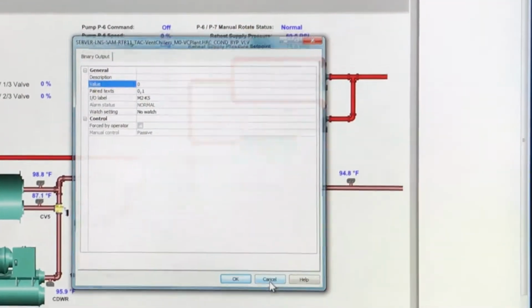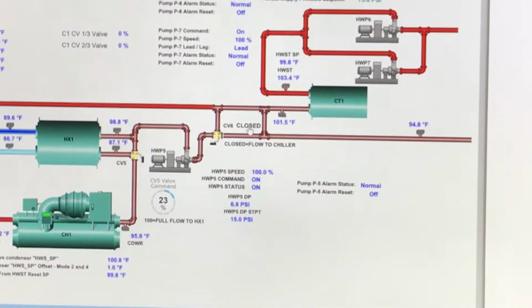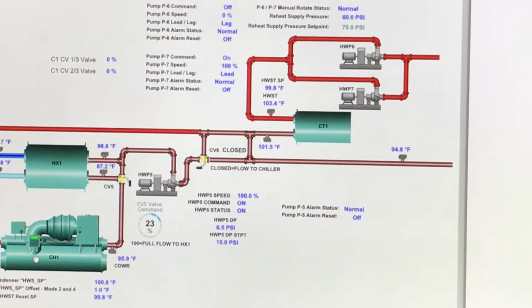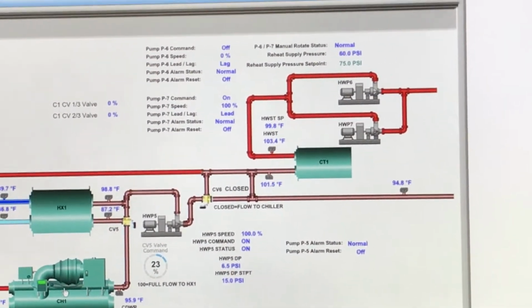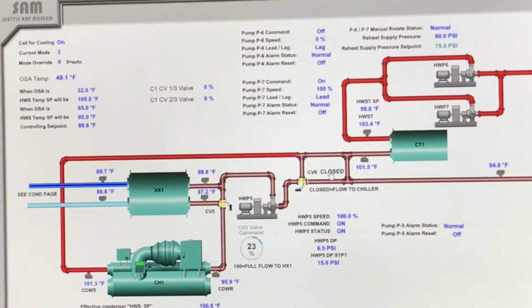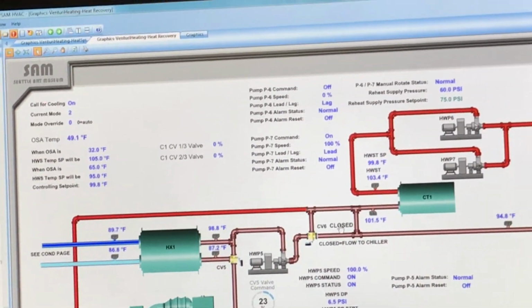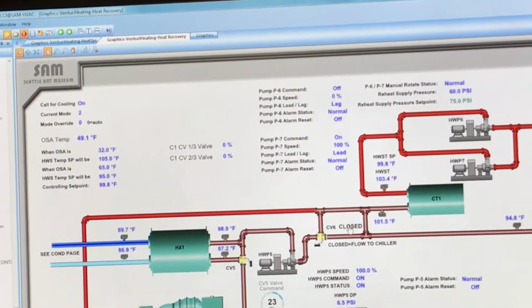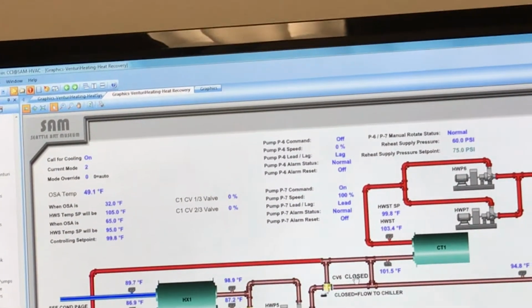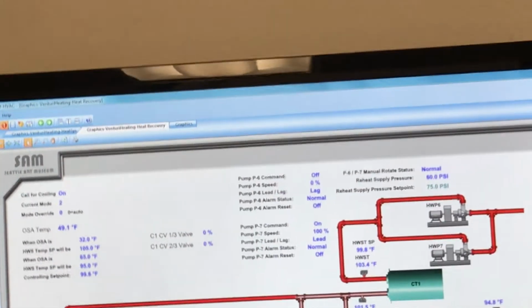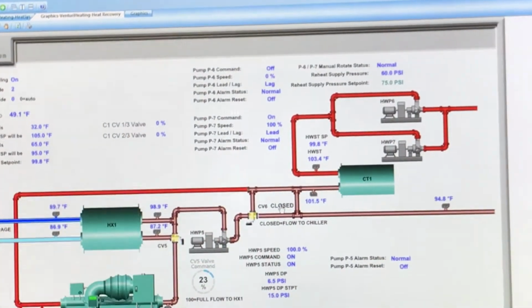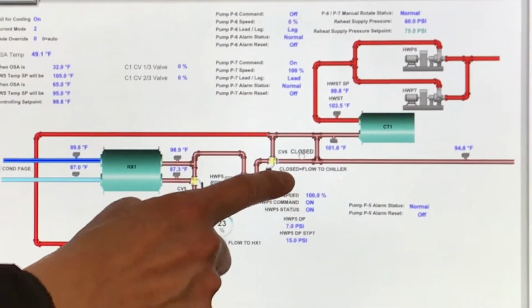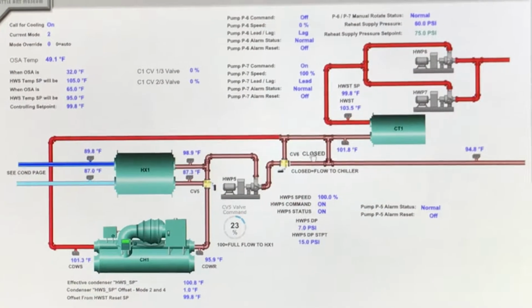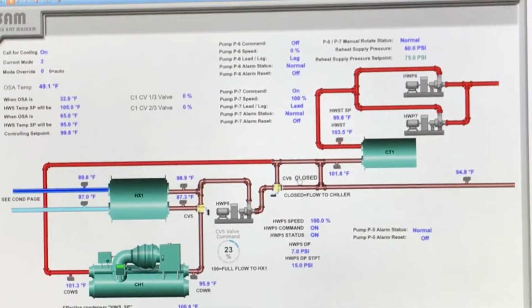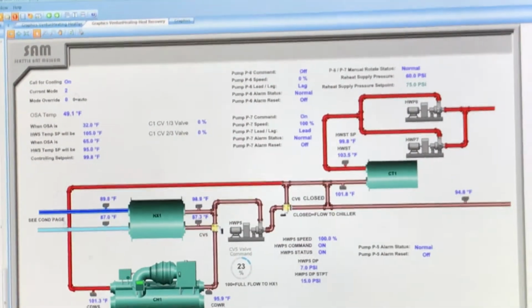Okay. So when it's closed, it's going through the chiller. In mode 6, you don't want it to go through the chiller, so it's going to be open. Yes, because this is a three-way valve, and so closed and open is really relative. The description here is that when it's closed, the flow is to the chiller. A little confusing, I know. Yes, a three-way valve is always a confusing control valve.